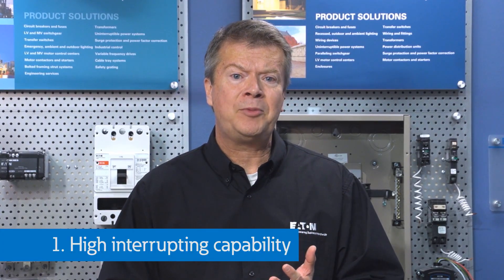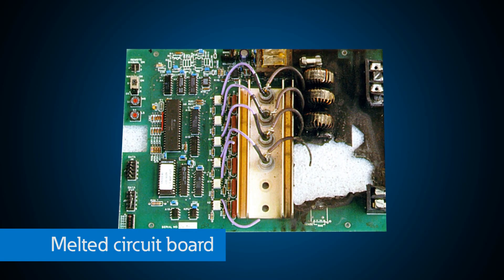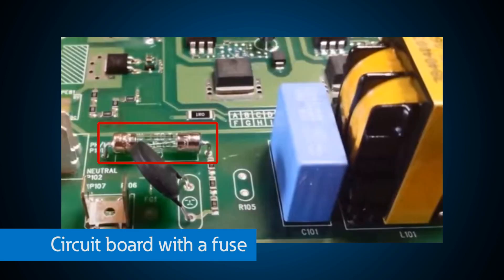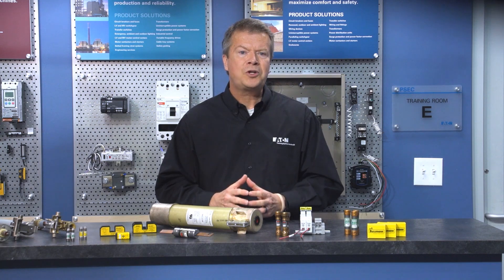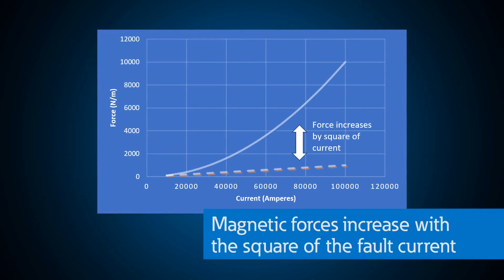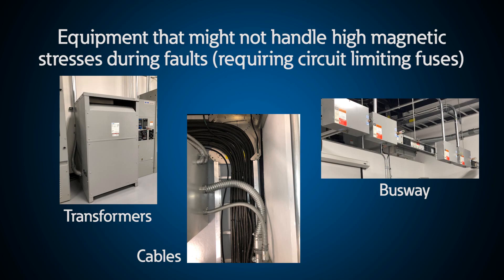Three key special needs: First, high interrupting capability — the closer to the utility service entrance, the higher the available fault current, so fuses are commonly found in service entrance switchboards and switchgear. Even on a small circuit board, 20 amps through a sensitive trace would be very destructive. Second, current limiting — magnetic forces during a fault increase by the square of the fault current, so products that can't tolerate those stresses use current-limiting fuses.